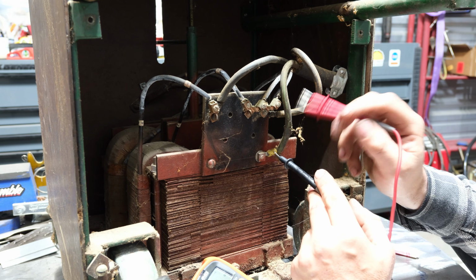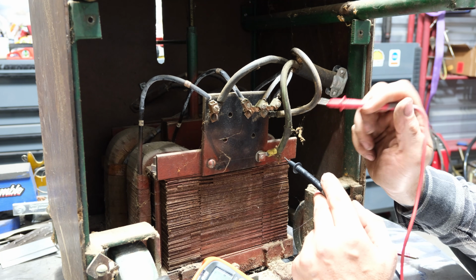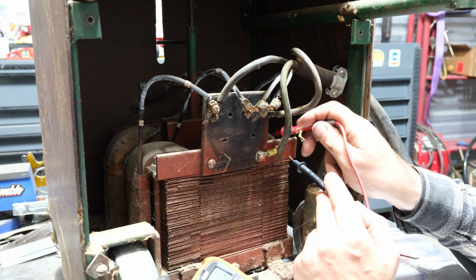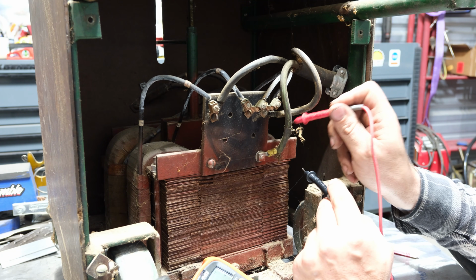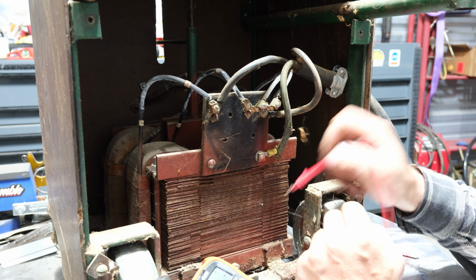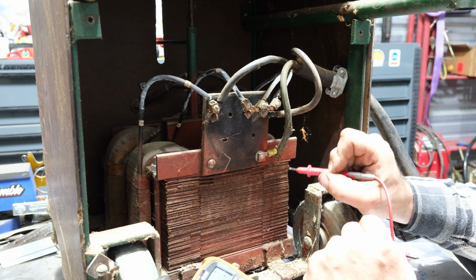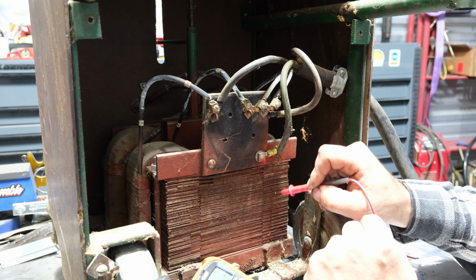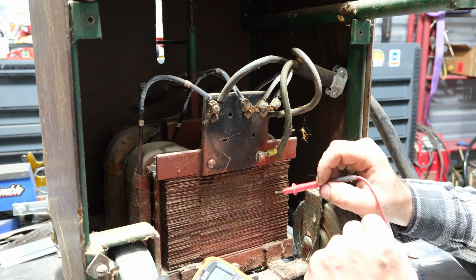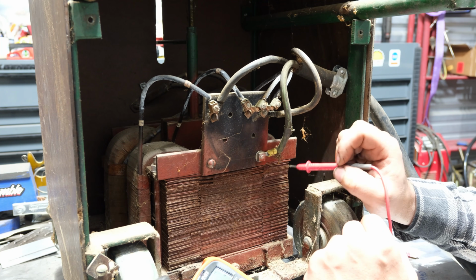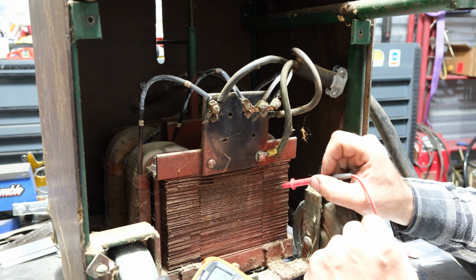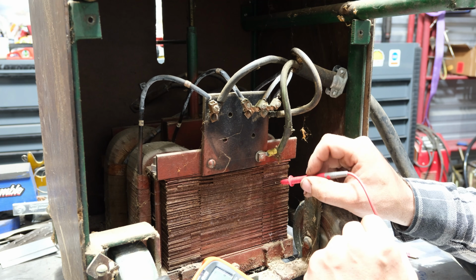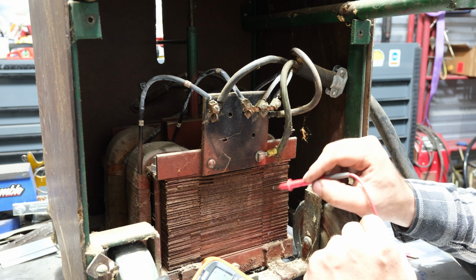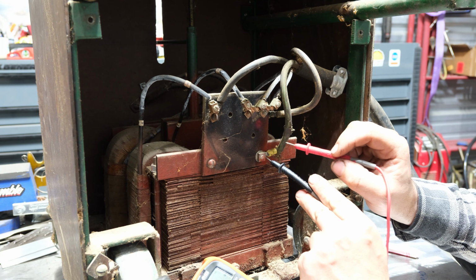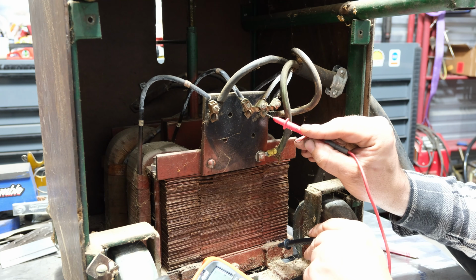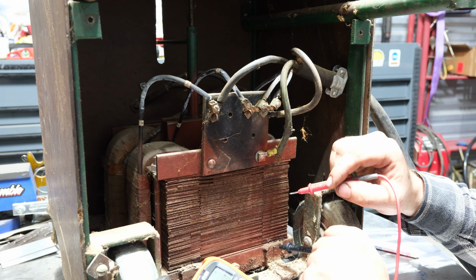That's a great sign. Now you guys got to remember that this hot wire, both of them that come in and power the primary coil on this transformer, that coil can over time short out to this core. Even though that's wire wrapped around the core on the primary, it's actually jacketed in some form. It could be a coating on a wire or cloth wrapped, whatever it is, that is electrically isolated from this core. And if there is a short in it at all to ground, we would see continuity between like this case and the hot wire, and we do not. So that's a great sign.